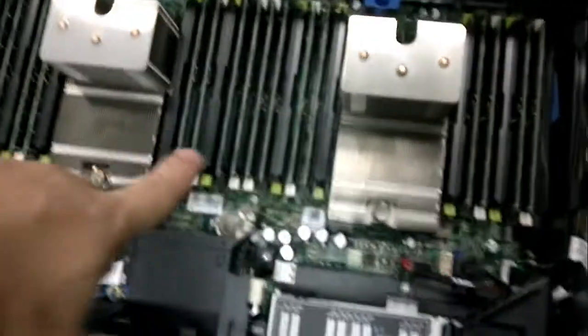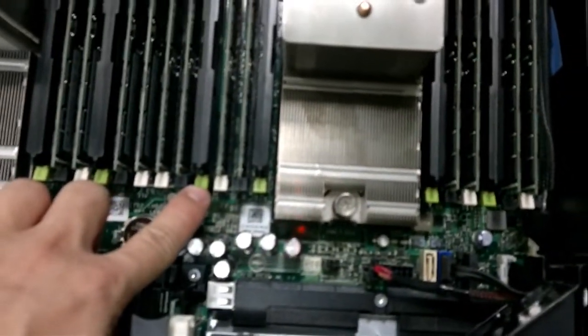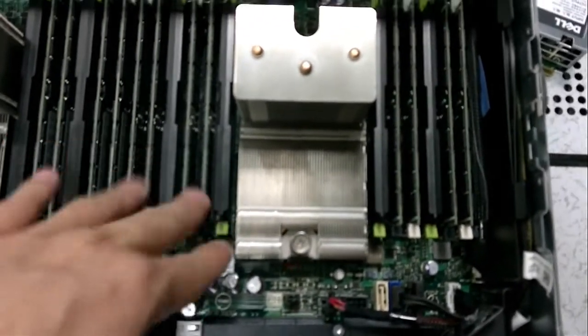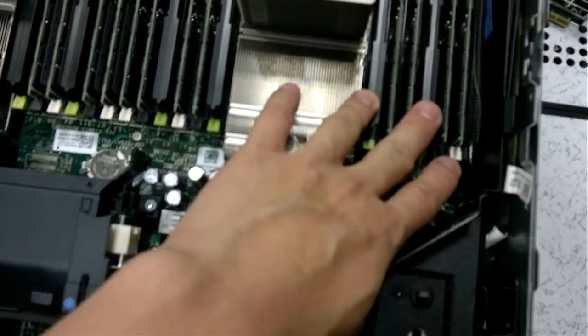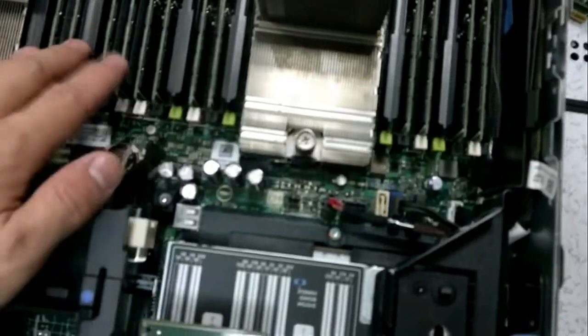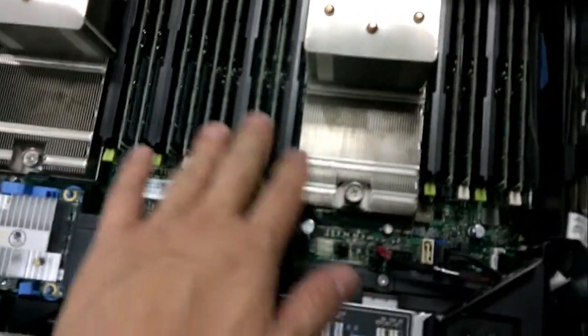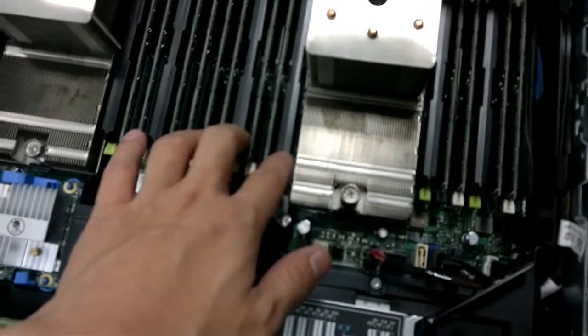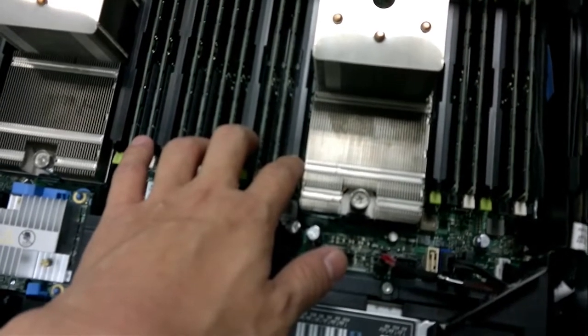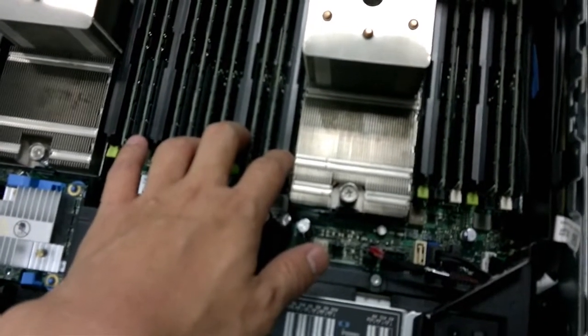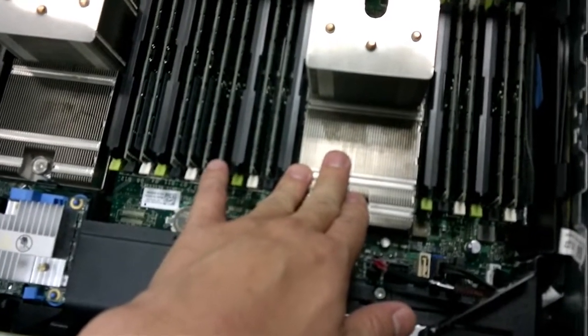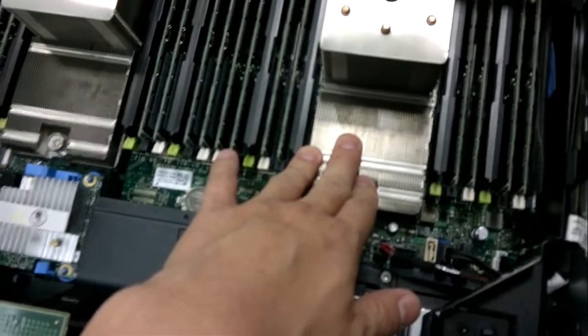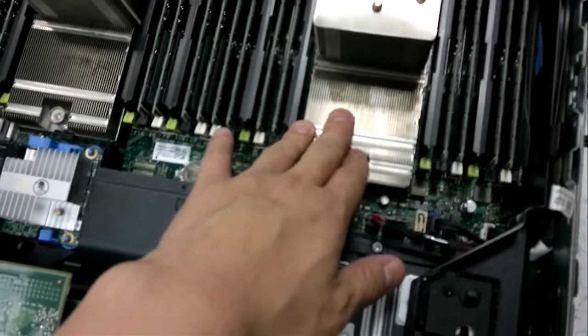Another key efficiency for this particular system is that you notice the green blank, this is the third slot. So all the third slots are not populated. They are about two, four, six, eight, yeah, eight slots not populated. So one reason they are not populated is because this DIMM is actually low voltage DIMM operating at 1.35 volt.